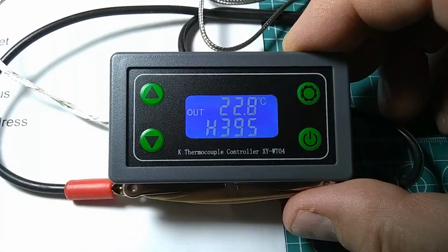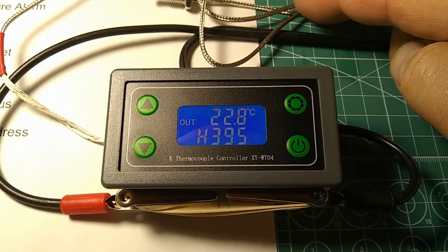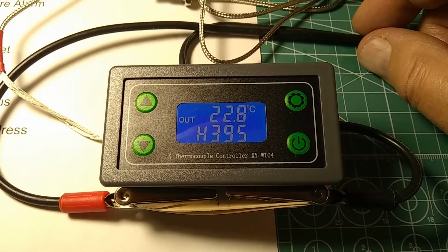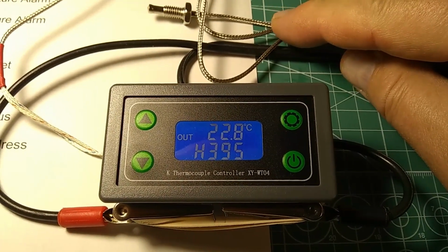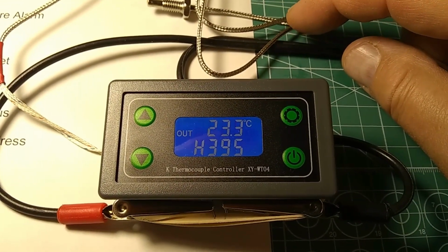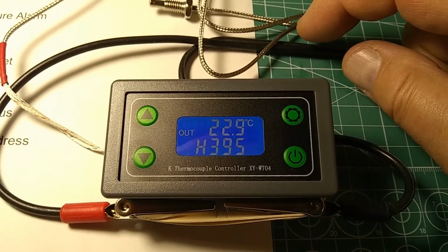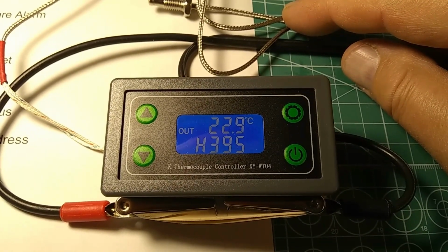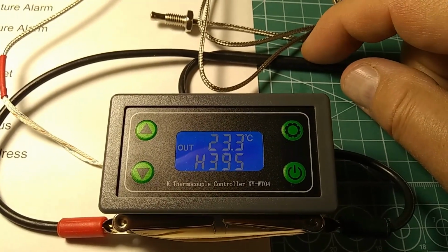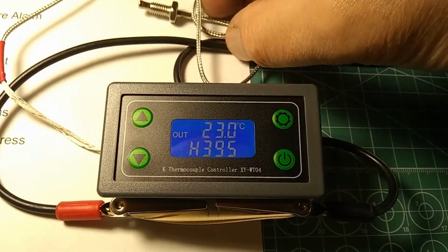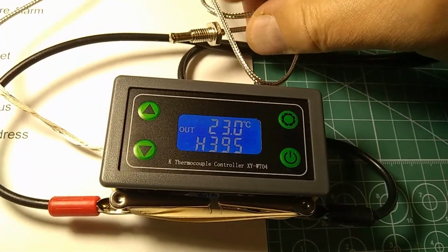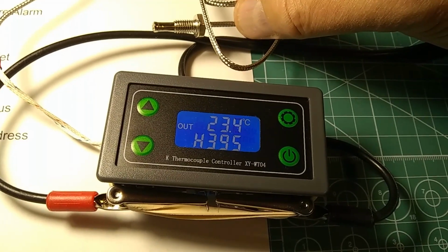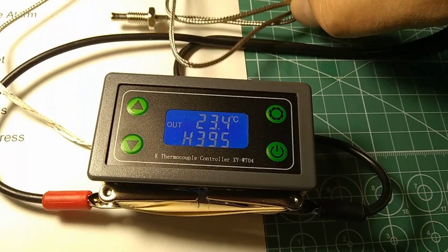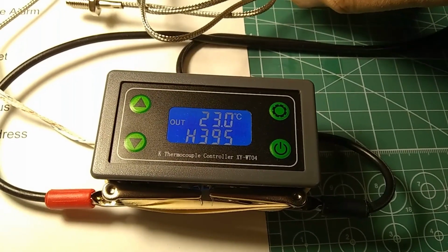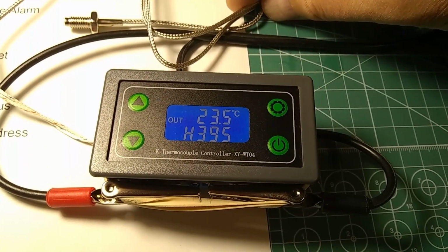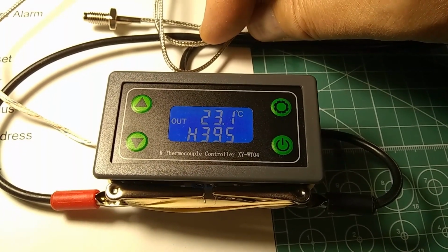It's a high temperature controller, but it goes down to minus 100 also, so it's got a good range. Now the difference between the thermistor and the thermocouple is that the thermistor will change its resistance with temperature, and a thermocouple actually generates tiny electrical voltage. It generates about 5 millivolts per each 100 degrees Celsius. So it is a tiny thermal cell. It will actually generate electricity, but the amounts are so tiny that the cable has to be nicely screened and shrouded, and there's a high precision in reading what comes from the thermocouple probe.